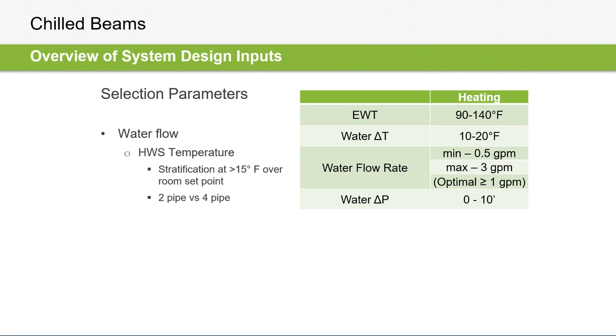And in my experience, I don't really have a huge preference on these. There are some downsides to the 2-pipe with the changeover. You will have some crossover in the medium. If you're using different levels of glycol, or a glycol in heating and no glycol water in cooling, you will have some cross-contamination with that 2-pipe system if you do a changeover. So that's one thing to consider.